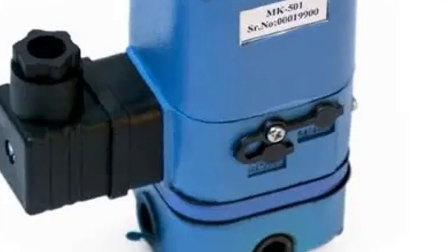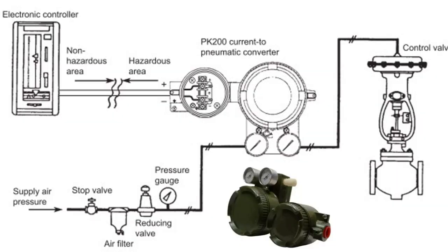Don't forget about calibration drift. IP converters aren't set and forget devices. As components age or if temperatures swing wildly, you'll see your output pressure start to wander. If your system's acting up and everything else checks out, it might just be time to recalibrate.